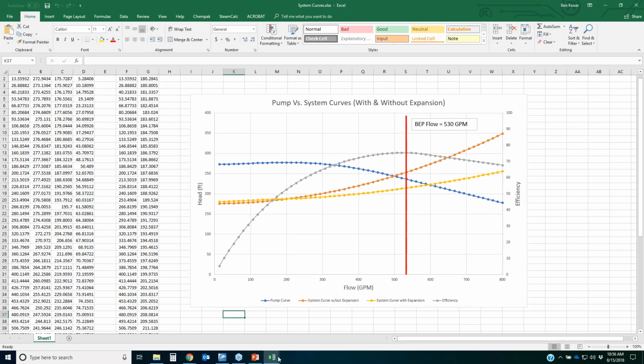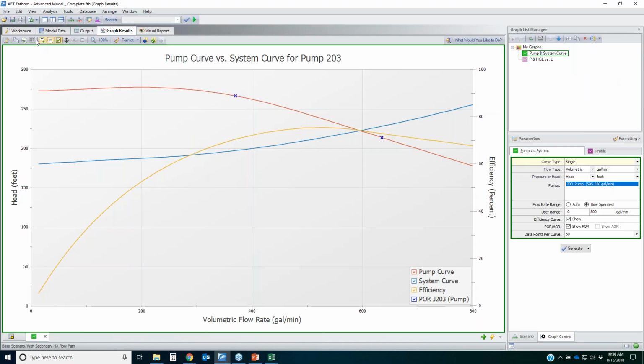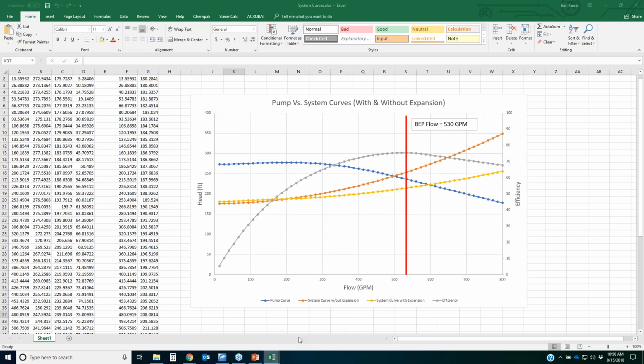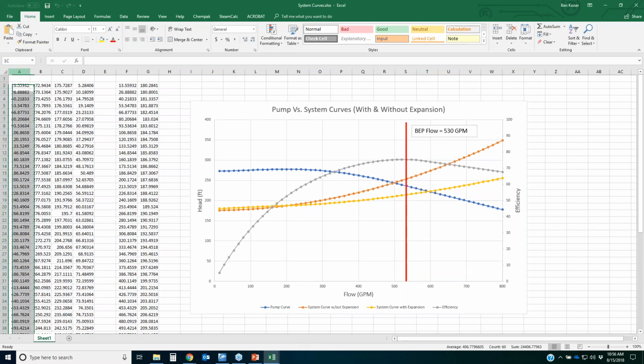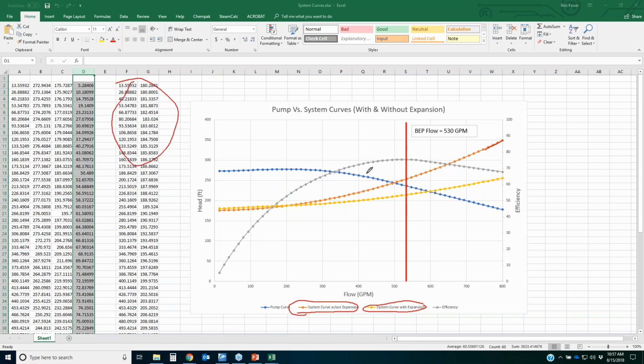Okay. So what I did was in Fathom, I simply went to this button right here and I said copy the XY data and I pasted it right into Excel. So I've got my flow rate, this is my pump head curve, this is my system curve, and this is my efficiency curve. Okay, the orange dotted line right here is my initial system curve without the expansion. Okay, so that's this line right here. The yellow line, this is my system curve with an expansion.